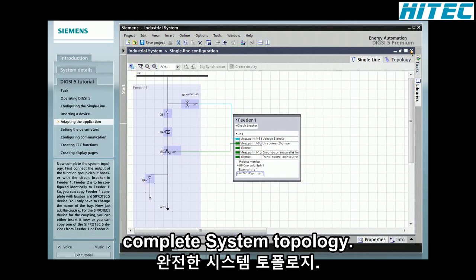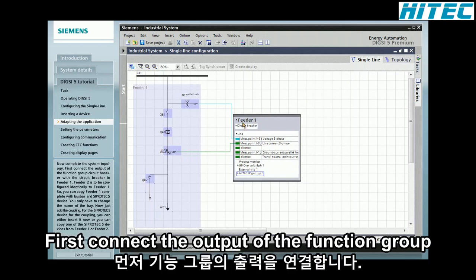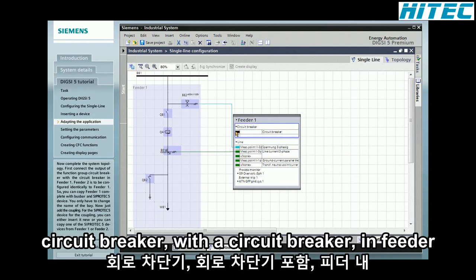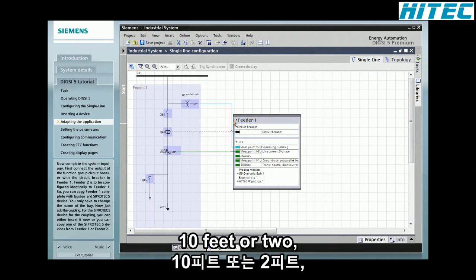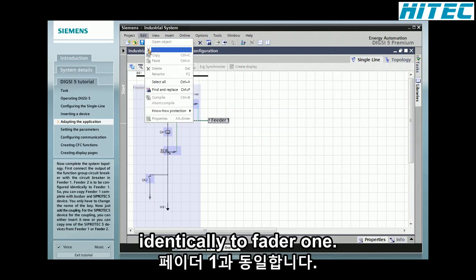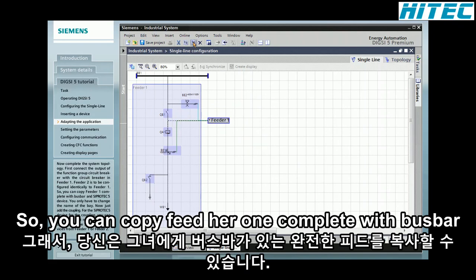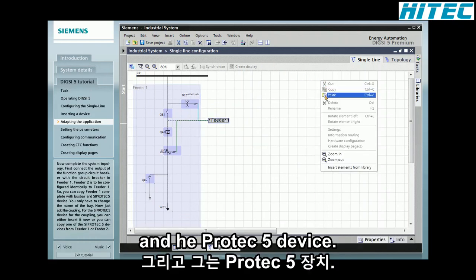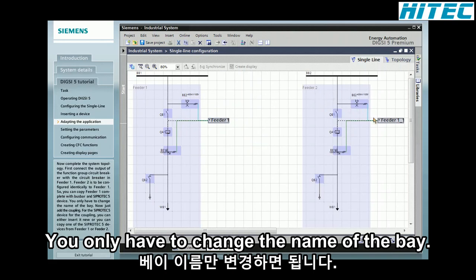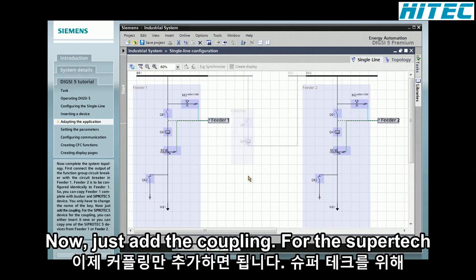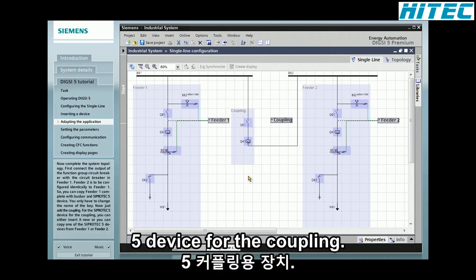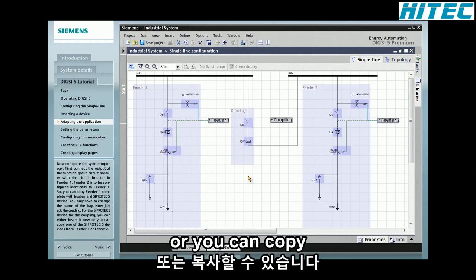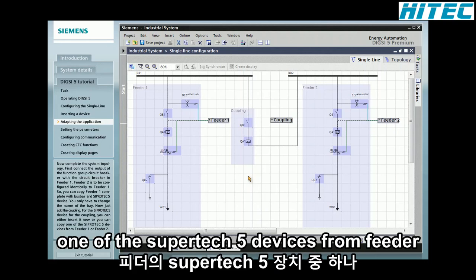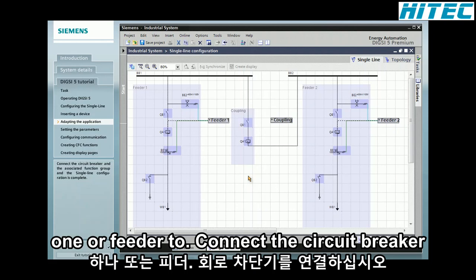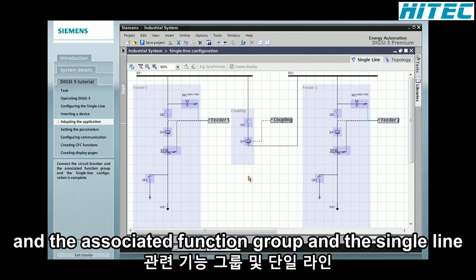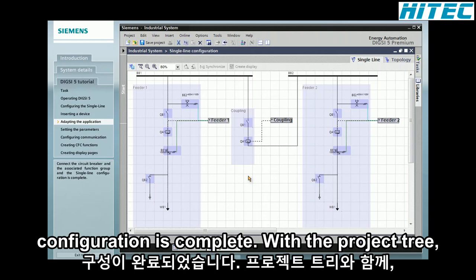Now complete the system topology. First, connect the output of the function group circuit breaker with the circuit breaker in feeder 1. Feeder 2 is to be configured identically to feeder 1. So you can copy feeder 1 complete with busbar and SIPROTEC 5 device. You only have to change the name of the bay. Now just add the coupling. For the SIPROTEC 5 device for the coupling, you can either insert it new or you can copy one of the SIPROTEC 5 devices from feeder 1 or feeder 2. Connect the circuit breaker and the associated function group, and the single-line configuration is complete.